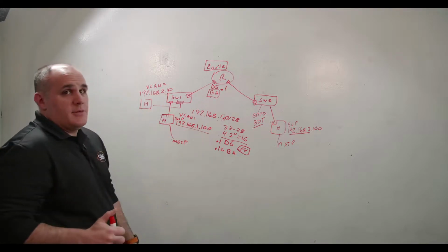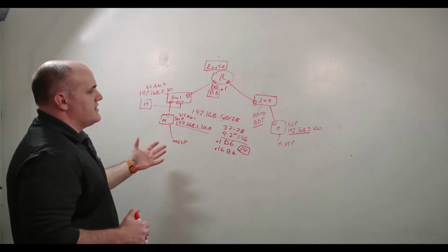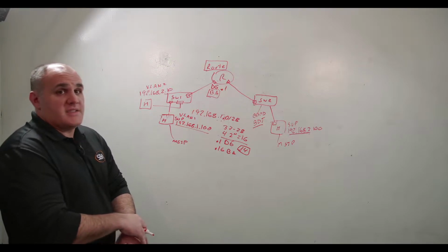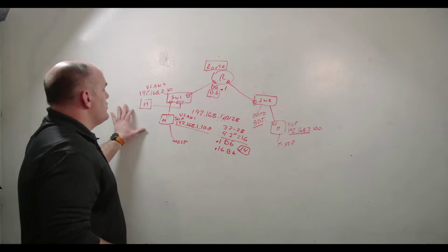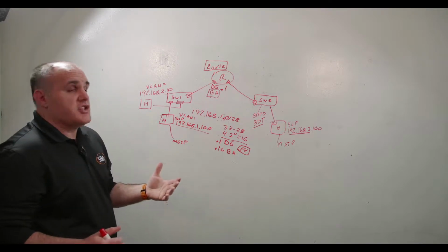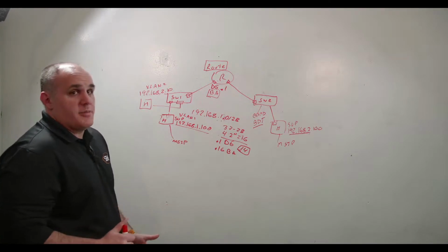This is how IT will do a lot of things because you're not going to get all of your devices and drops on their switch, especially if you're using a ring or a bus IP architecture. Then you're typically going to have 1 to 2 ports on their switch, and the rest of the ports are actually going to be other VLANs, typically for their business systems or other building systems.